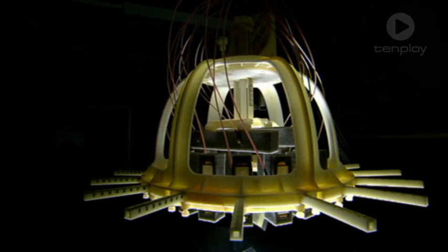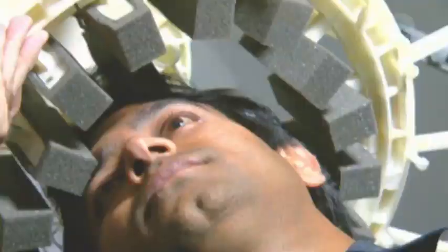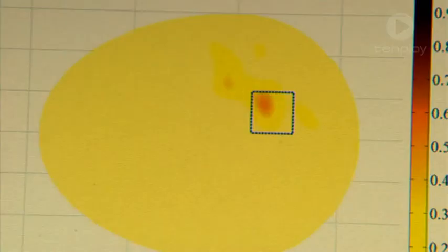It's a portable imaging system that allows us to see if a bleed has occurred in the brain. It relies on electromagnetic sensors — there are 16 of them around the head and four above. These sensors are small antennas, sending and receiving low-intensity electrical signals, which scans the brain in seconds. Each sensor is mounted on a movable rod so that it can be quickly adjusted to anyone's head size. The system works thanks to dielectric contrast — that's where some matter, like blood, appears more dense to electric fields than other matter. So a hemorrhage will show up darker than the healthy tissue surrounding it. Each sensor sends and receives signals into the cranium, up to 200 pulses per second.